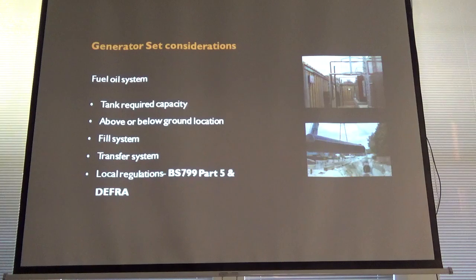And again, it's the what if. With this riser, you actually have a sort of elbow section there in a leak detection. So if that inner skin fails, you want to know. You want to know there's been a leak and where it is, to track it, to find it. The biggest single thing with this legislation is, and I did it on one site, you have a customer that says, I don't want double skinned, leave it single. Okay, it's fine. We had to ask the questions of duty of care.